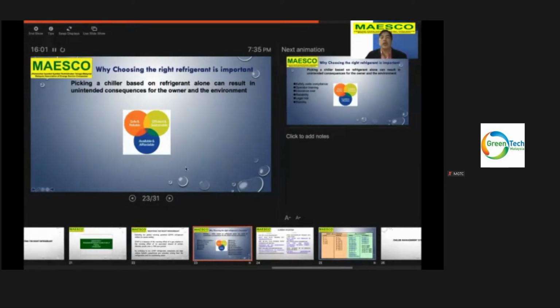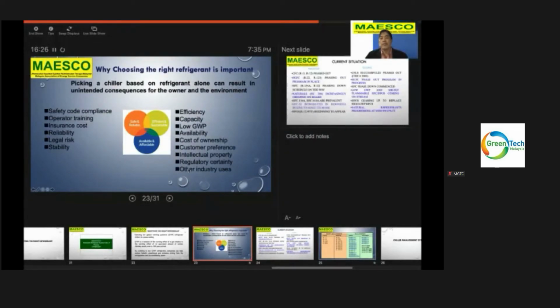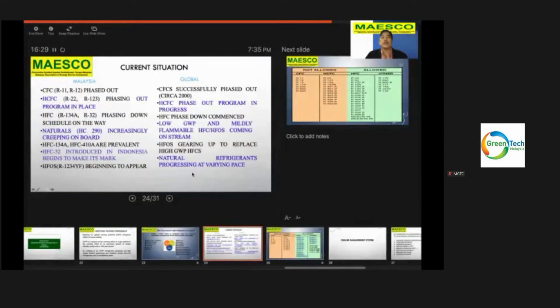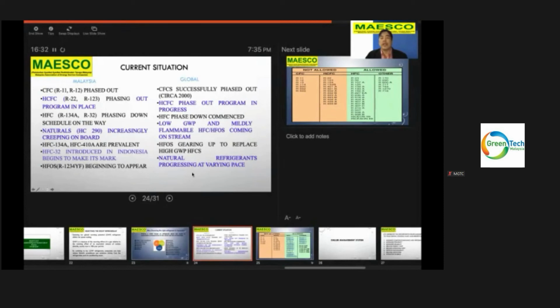Picking a chiller based on refrigerant alone can result in unintended consequences for the owner and the environment. You need to know, there are many parameters why we have to choose the right refrigerant. It can be safety code compliance, operator training, insurance costs, reliability, legal risk, stability, efficiency, capacity, low GWP, and many more. Now, if you look at the Malaysian standard, CFC R11, R12 have already been phased out. In the Malaysian context, for R22 and R123 a phasing out program is in place. And for R134a and R32 a phasing down schedule is on the way.